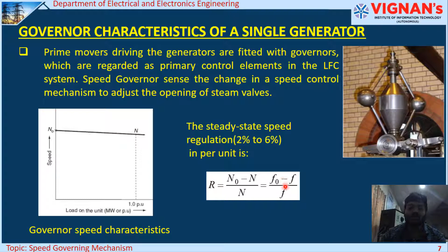Here you can observe that when the load is zero, that is when the load is not there, the speed is denoted by N naught, which is called the no load speed. Now as the load is increased to its rated value, the speed is reduced from the no load value. This reduction in the speed, or the change in the frequency with the change in the load, is generally called speed regulation. The speed regulation must be within 2% to 6% per unit for a power system. It can also be taken as no load speed minus full load speed by full load speed, or no load frequency minus full load frequency by full load frequency.